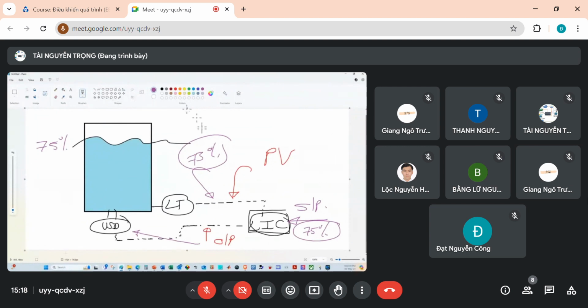Or just the opposite: if my level was sitting at 80%, now I am above the set point. My controller knows to send a signal to the variable speed drive to speed it up somewhat, which drops the level down to 75%. There are many different examples of process control out in the field -- it can be as simple or as difficult as you like.